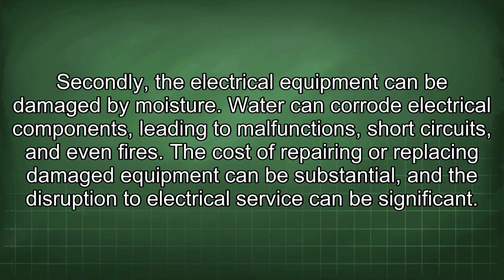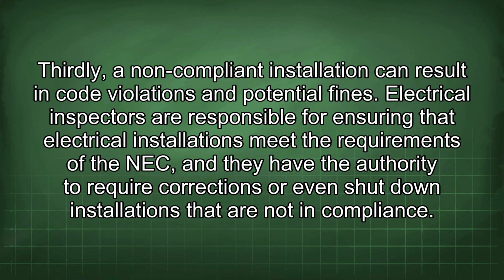Secondly, the electrical equipment can be damaged by moisture. Water can corrode electrical components, leading to malfunctions, short circuits, and even fires. The cost of repairing or replacing damaged equipment can be substantial, and the disruption to electrical service can be significant. Thirdly, a non-compliant installation can result in code violations and potential fines. Electrical inspectors are responsible for ensuring that electrical installations meet the requirements of the NEC, and they have the authority to require corrections or even shut down installations that are not in compliance.